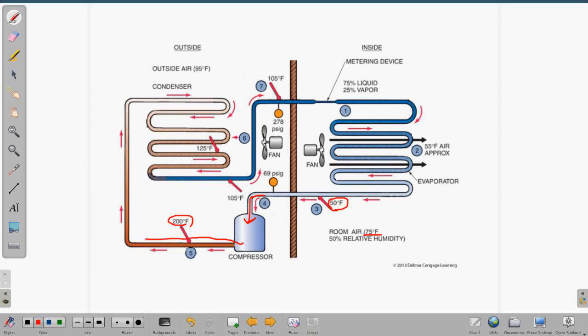And at the beginning part of the condenser coil right here, we are de-superheating, so we're taking away all this superheat that we added from this point to the compressor. We're going to de-superheat it at the beginning and bring it to the saturation point of the refrigerant. Since we removed all the superheat, the sensible heat, about 75 degrees, the refrigerant is now at a temperature of about 125 degrees. So in this refrigeration cycle, at saturation, now all of the latent heat can be shed.